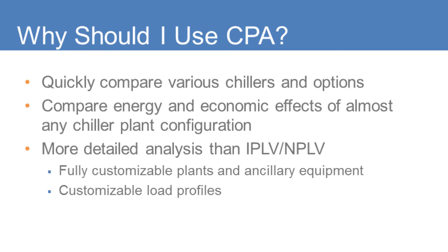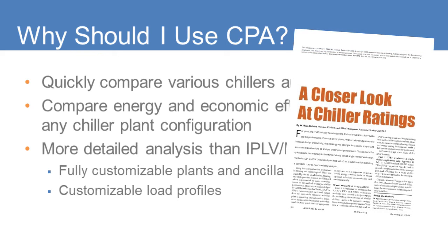The IPLV value was not intended to be used to predict the annualized energy consumption of a chiller in any specific application or operating conditions. It does not take into account any specific weather location or building load profile like Chiller Plant Analyzer does. For more information on why IPLV and NPLV should not be used for energy analysis, see the AHRI Standard 550-590 Appendix D and the ASHRAE Journal article titled A Closer Look at Chiller Ratings.